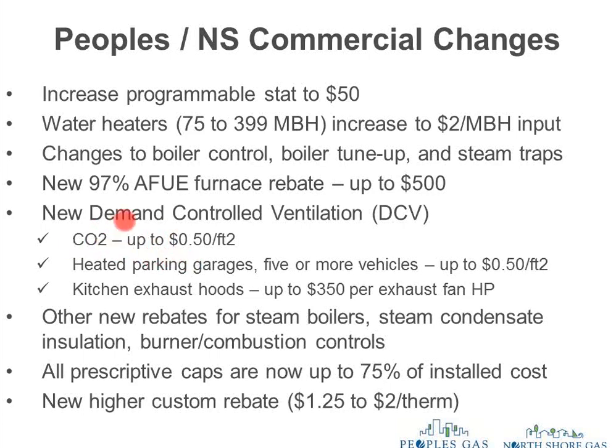But in addition to CO2-based demand control ventilation, which is what you'd use in schools, auditoriums, retail, restaurant dining rooms, that kind of stuff, there's also a DCV rebate that's new for heated parking garages. You can get 50 cents per square foot there. Obviously, in that case, we're not using CO2 sensors. We're using carbon monoxide sensors, or if it's diesel vehicles, we're using nitrogen dioxide sensors. And there's also a DCV rebate for kitchen hood exhausts. It's $350 per exhaust fan horsepower. The idea there, obviously, is the less I exhaust out, the less makeup air I need, the less natural gas I've got to buy for the makeup air. That's why it's on this program.